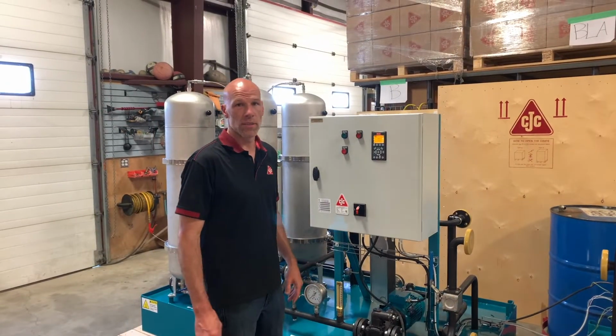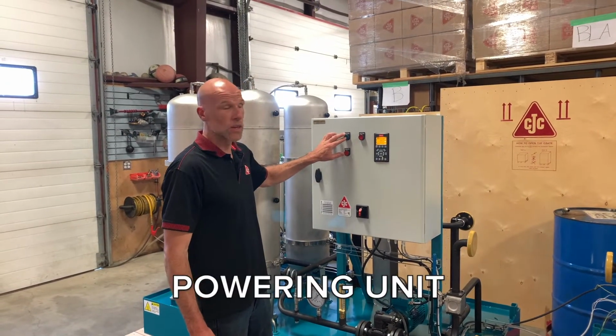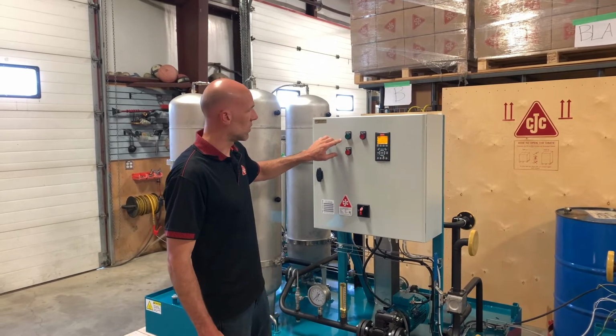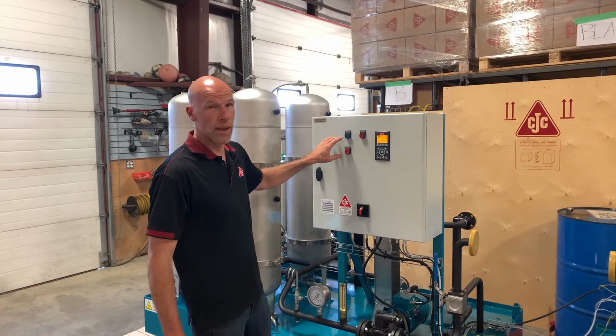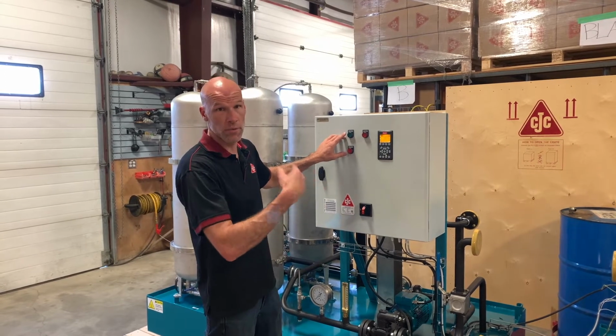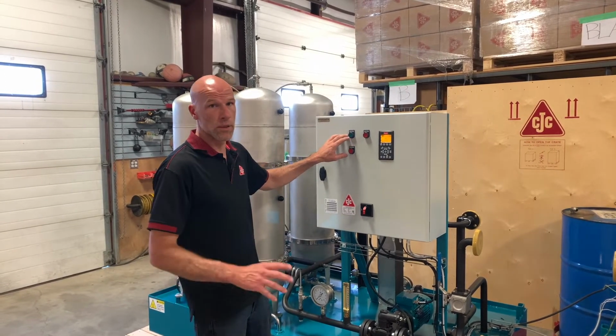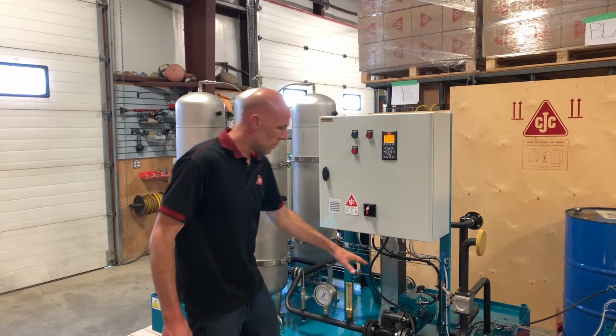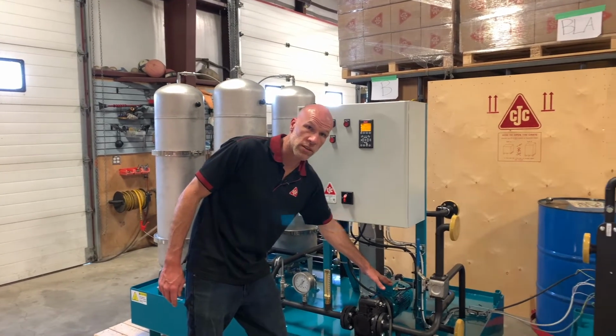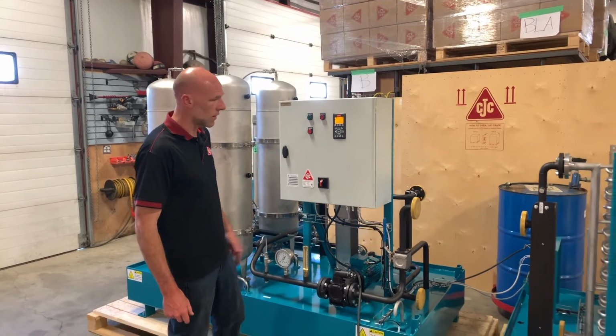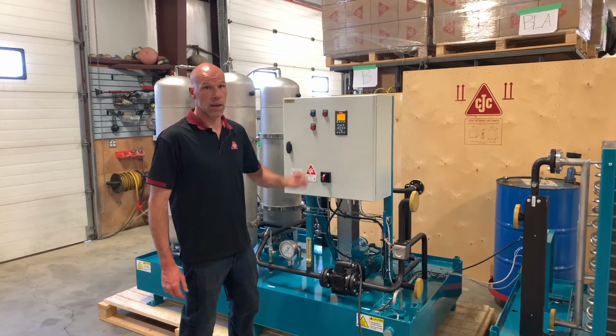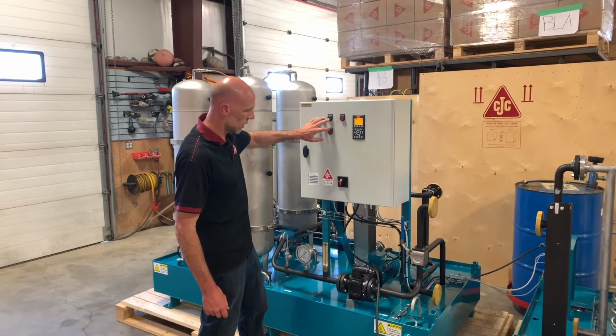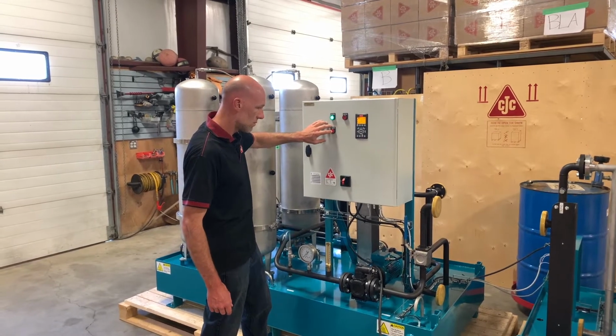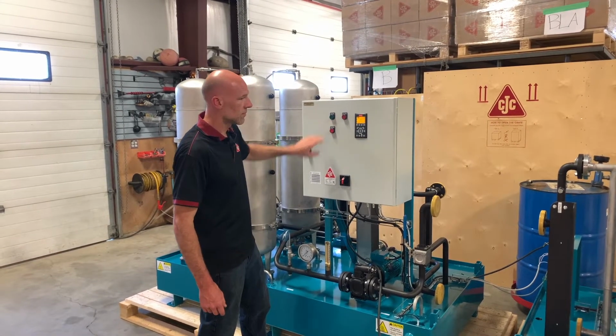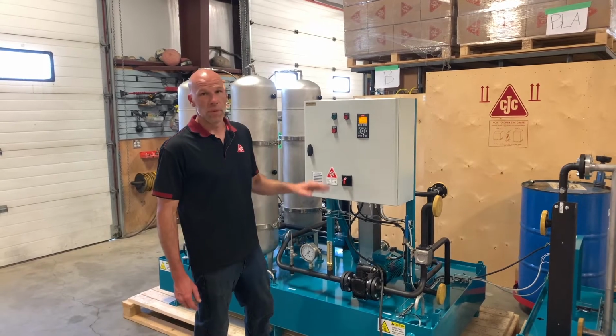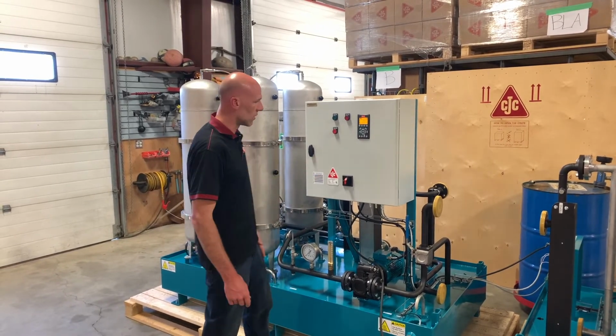When you're ready to power on the unit, give it a bump first to make sure that your motors are in fact turning the right direction. And sometimes it can be helpful to have somebody nearby confirming as the motor starts up to see visually which direction it's turning. The pump motor will always turn the correct rotation because the frequency drive takes care of that, but you want to make sure that the fan is in fact turning the right rotation. So give a quick bump. Once you've verified, then you're ready to start the unit.